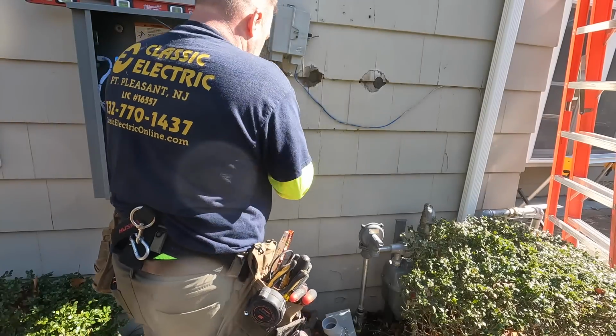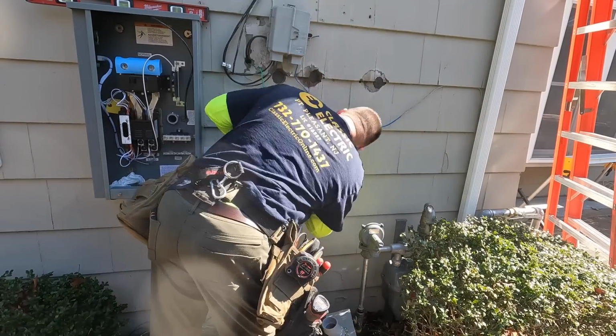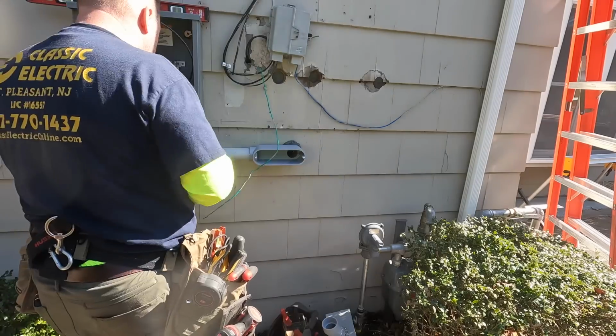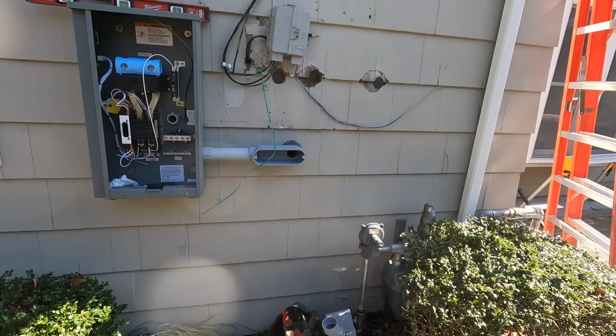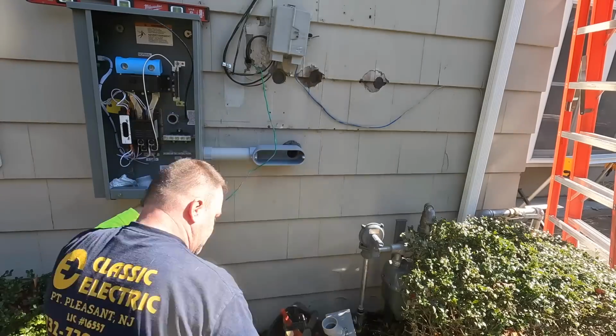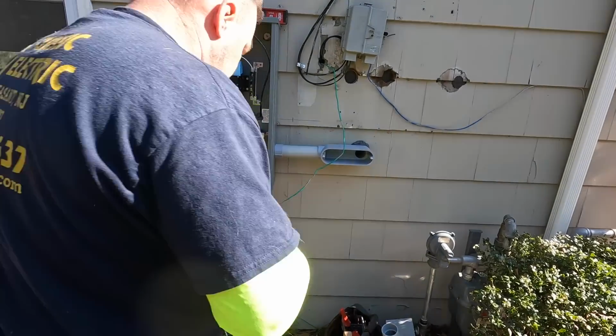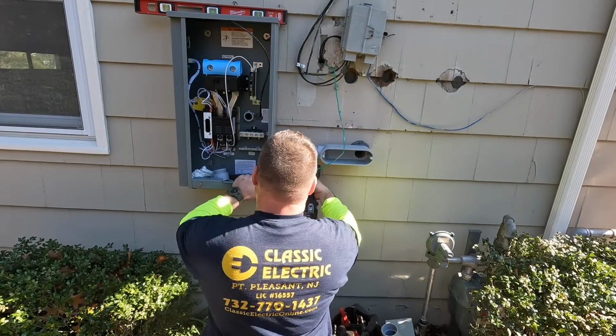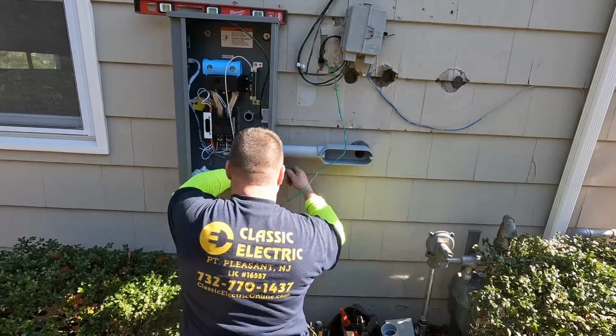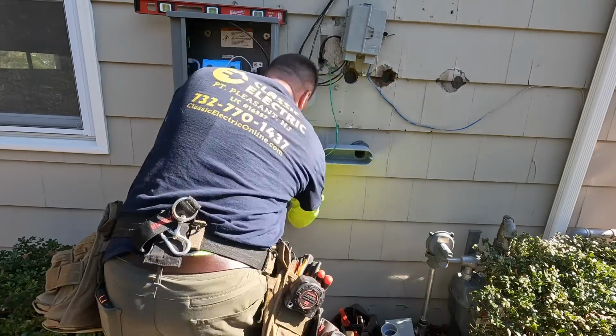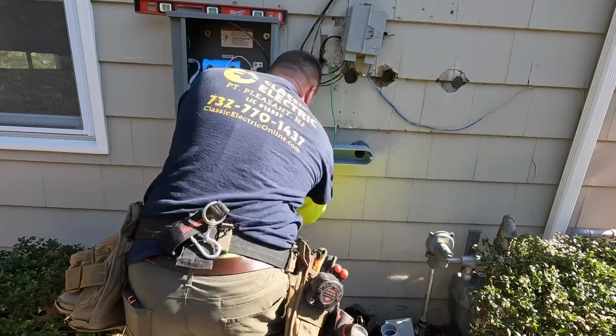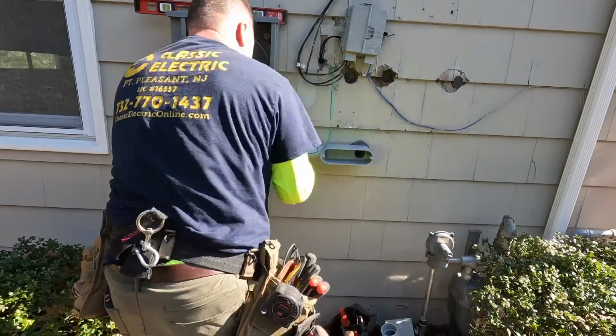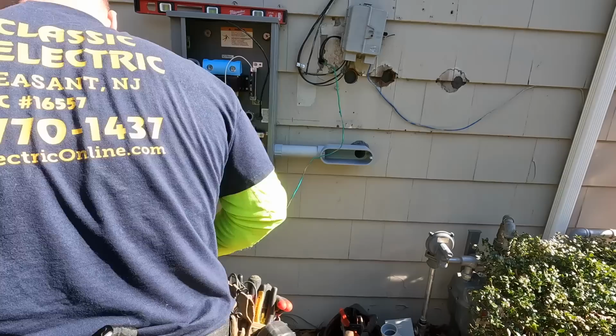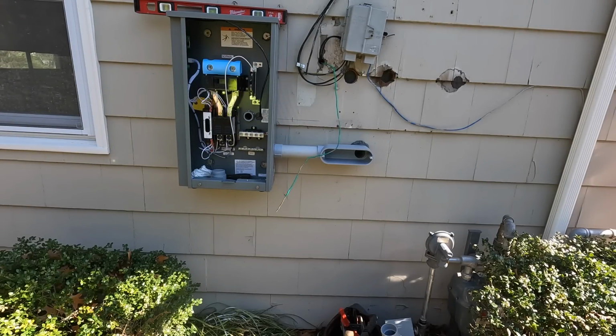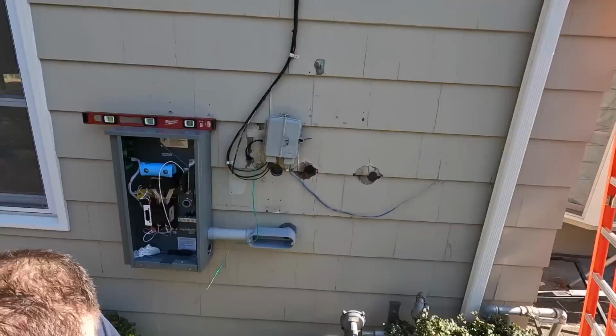Keep in mind too, when you're using the duct seal on the exterior, it must be rated for exterior use. Right on the packaging when you open it up, it should say indoor, outdoor usage. I know in New Jersey here, not all electrical inspectors ask for that, but some have in the past, and I'm able to produce a receipt or the package I have on the truck and show them it's this brand, so it's good for the outside.